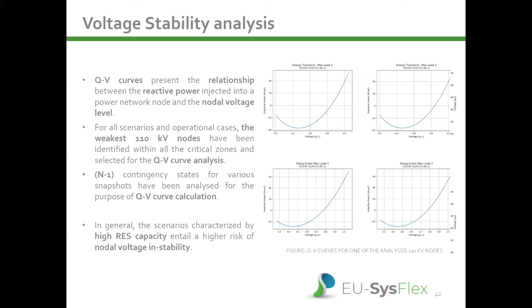We have also performed another analysis in order to assess the voltage stability margins in the 5 districts of the regional TSO control centers, called ODMs. In general, districts having more remote generation, like control center number 5, presented with the green curve, are characterized by lower voltage stability margins. QV curves, which represent the relationship between the reactive power injected into a power network node and the node voltage level, showed us a general conclusion that scenarios characterized by high renewables capacity entail a higher risk of nodal voltage instability problems.